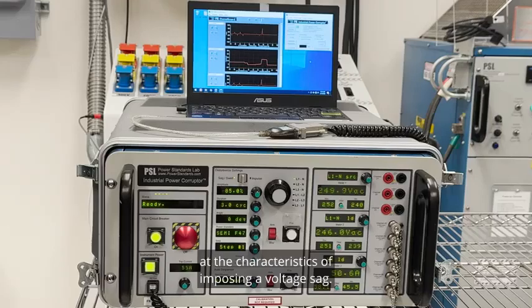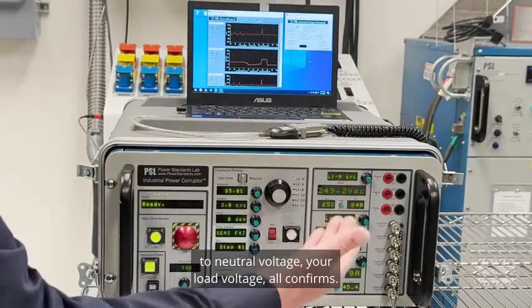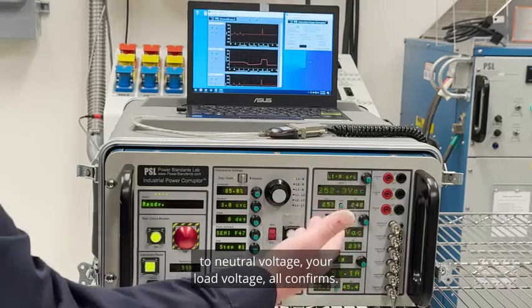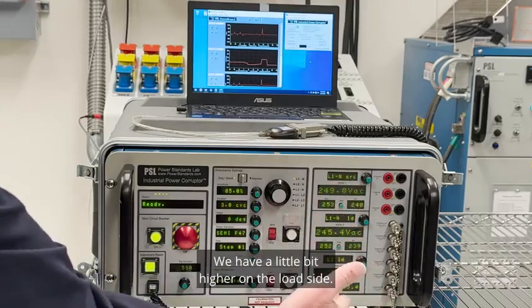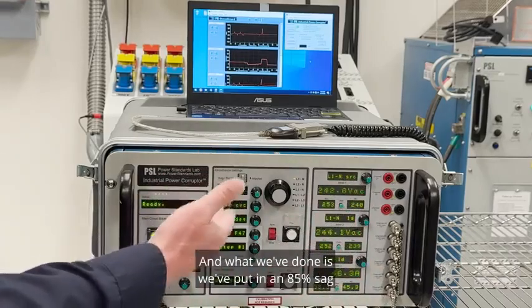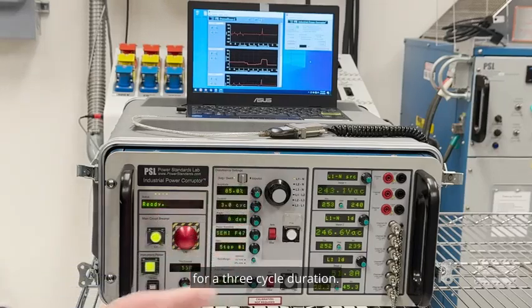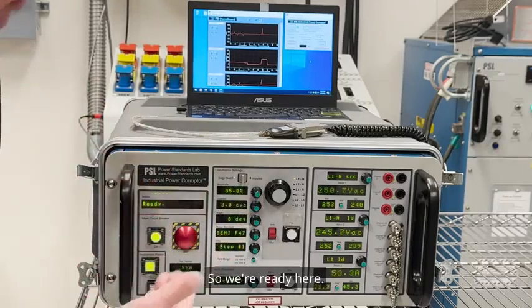What we have here, we've got your line to neutral voltage, your load voltage, all confirmed. We have a little bit higher on the load side. And what we've done is we've put in an 85 percent sag for a three cycle duration. So we're ready here.